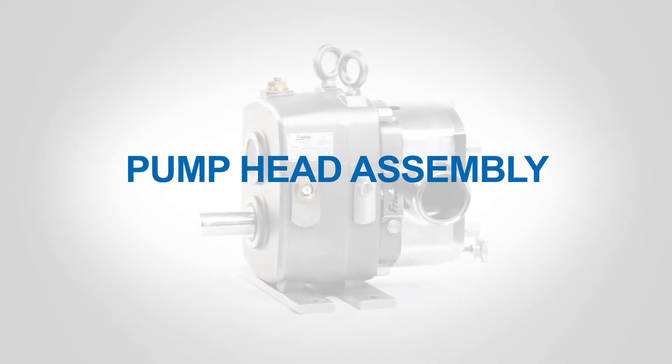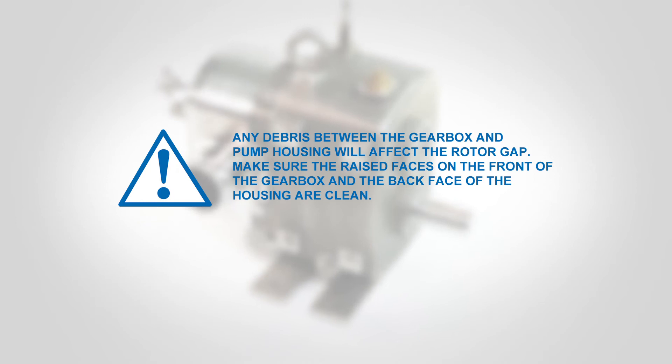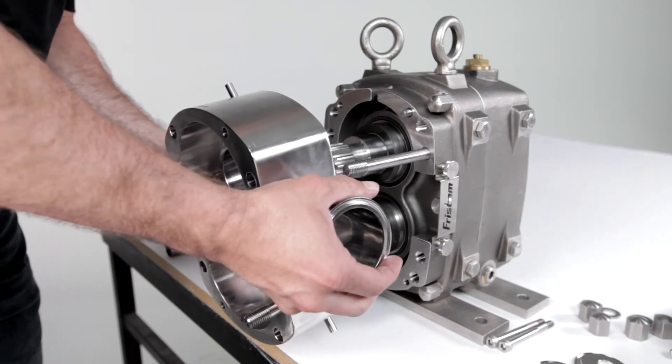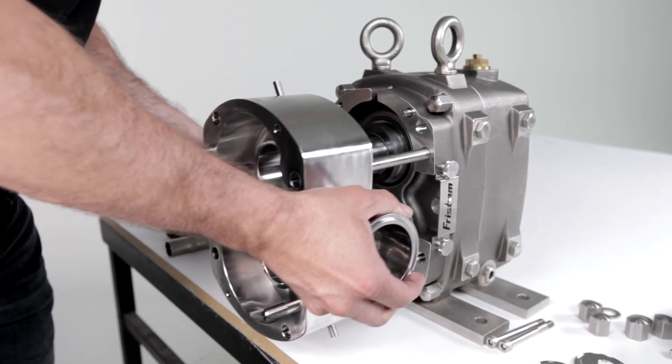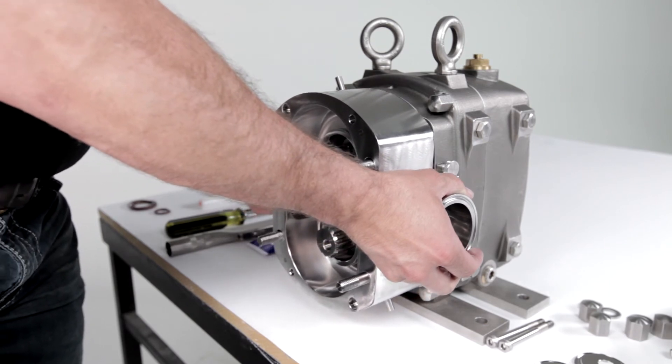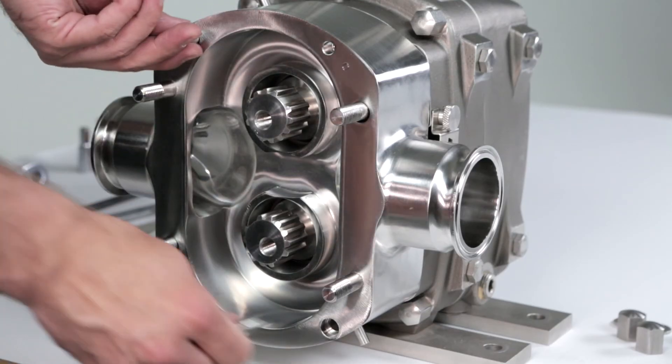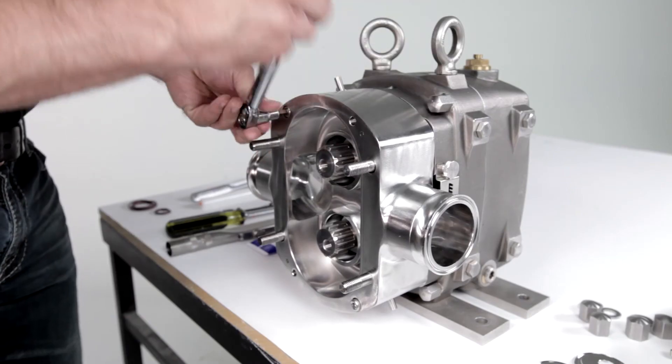Pump Head Assembly. Note any debris between the gearbox and pump housing will affect the rotor gap. Make sure the raised faces on the front of the gearbox and the back face of the housing are clean. Carefully slide the housing onto the studs and over the shafts with the serial number on top. Use a torque wrench to tighten the housing screws.